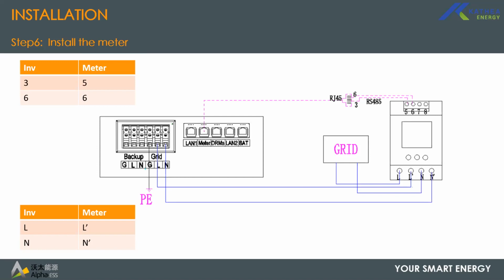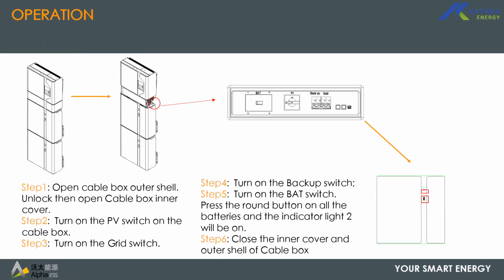It's a straight cable, 1 to 8 on either side should be the same. So you can wire it straight to the RJ45 plug-in. But in case the RJ45 plug-in doesn't fit in your DP port, then you can just remove it and take strand number 3 and 6 to 5 and 6 respectively. That's the RJ45 to RS485 conversion. So this is how the system looks when installed.